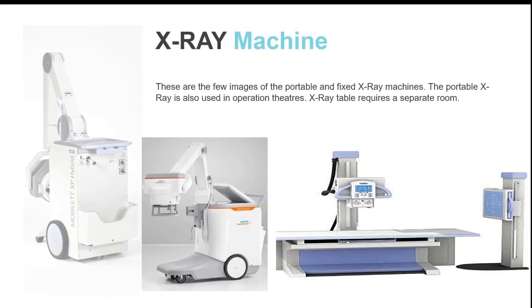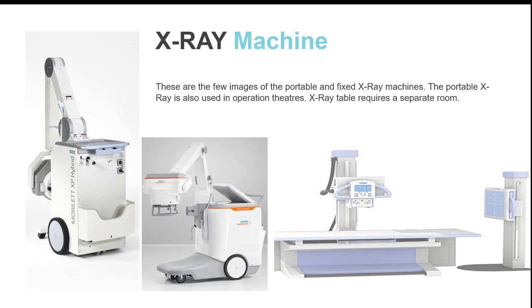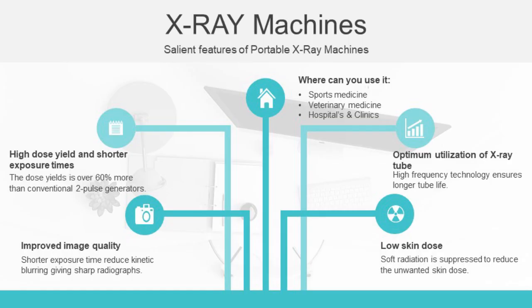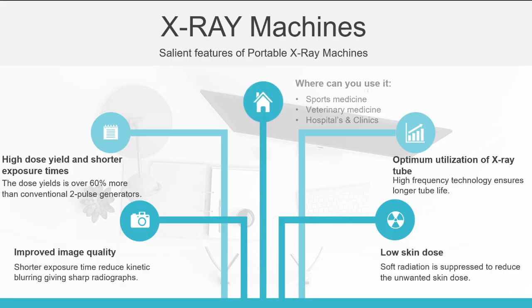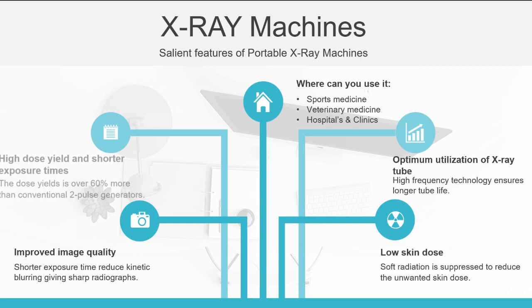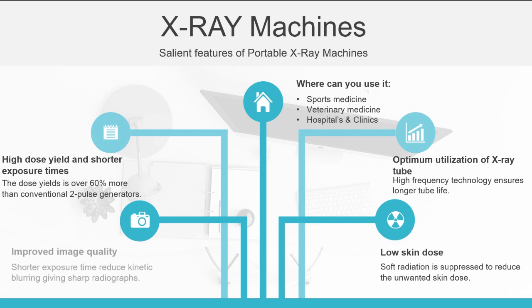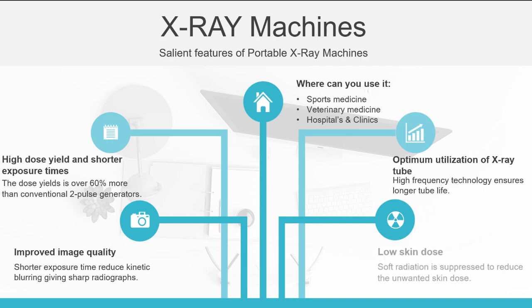These are a few images of portable and fixed X-ray machines. The portable X-ray is also used in operation theatres. It should be noted that an X-ray table always requires a separate room. Salient features of portable X-ray machines: they can be used in sports medicine, veterinary medicine, hospitals and clinics. They have a high dose yield and shorter exposure time — the dose yield is over 60% more than conventional two-pulse generators. High frequency technology ensures longer tube life. Shorter exposure time also reduces kinetic blurring, giving sharper radiographs, and soft radiation is suppressed to reduce the unwanted skin dose.